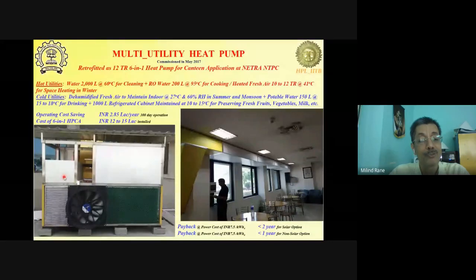The cooling effect stored was used for catering to the potable chilled water delivery, as well as for maintaining the refrigerated cabinet. And the heat stored in this was used for delivering 60-degree hot water as well as 95-degree cooking water. So the beauty of this was, without any complications of pumps, recirculation, and so on and so forth, we are able to deliver the hot water, chilled water, air conditioning as and when required, even when the compressor was not operating for air conditioning purpose.